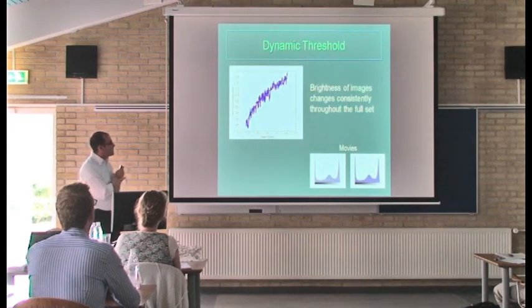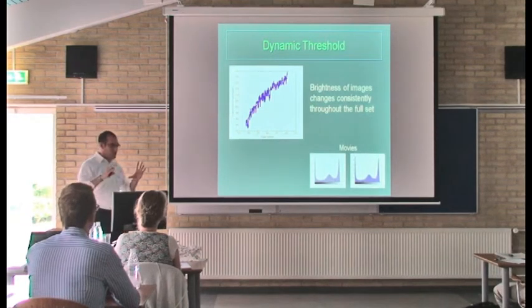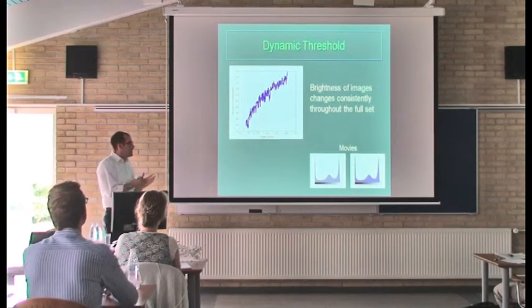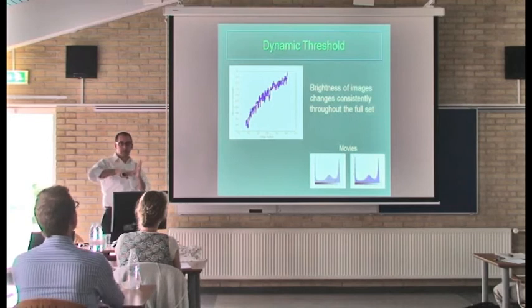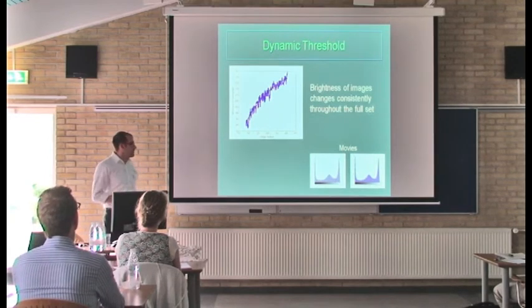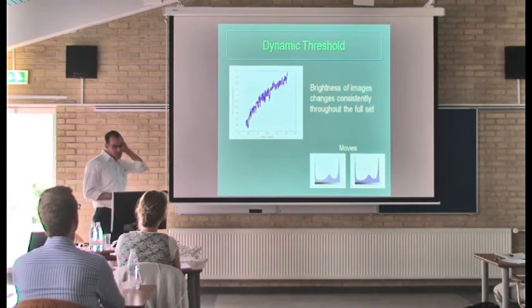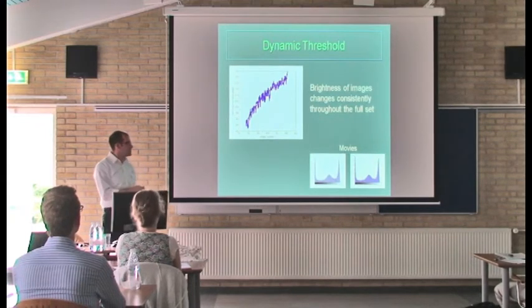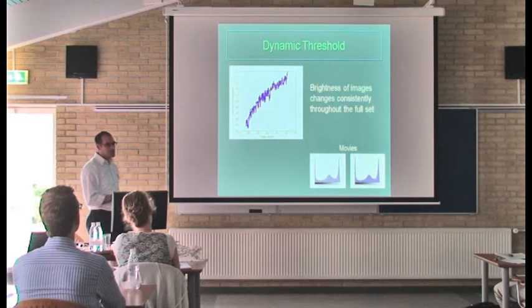I think this is the last image processing highlight I'm going to show. So we showed that you get sort of illumination changes on a single image, but you can also, throughout your set of images, get changing brightness between all your images. And this is something that came up on a recent data set we got. A lot of our earlier ones, we didn't see this, and not really sure why it happens. It could just be a function of the detector you're using. You're milling out more material, so it's a bigger trench, and so you can get more electrons out. But generally, the brightness was increasing.